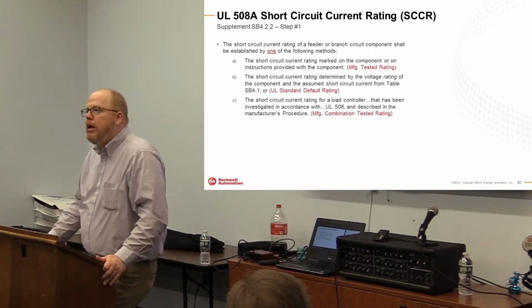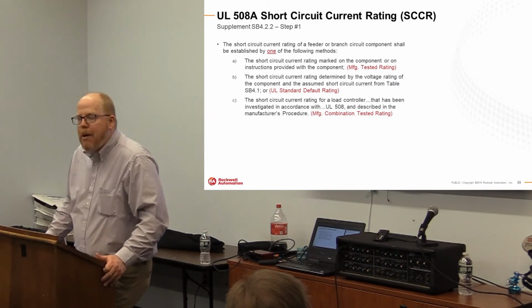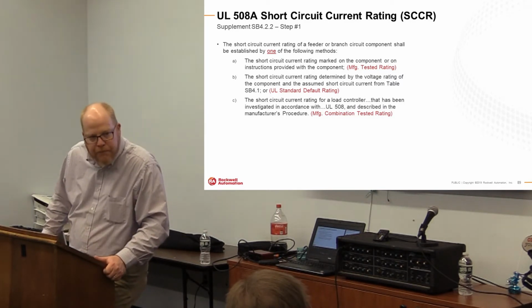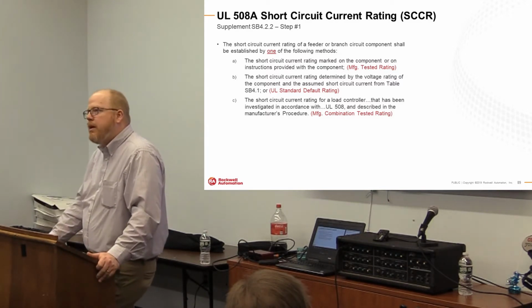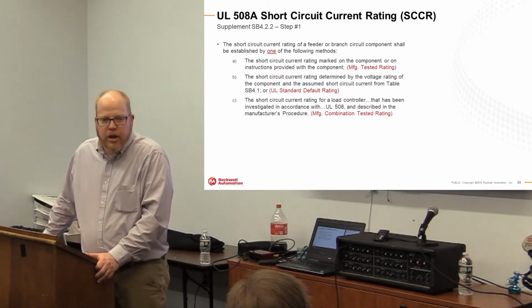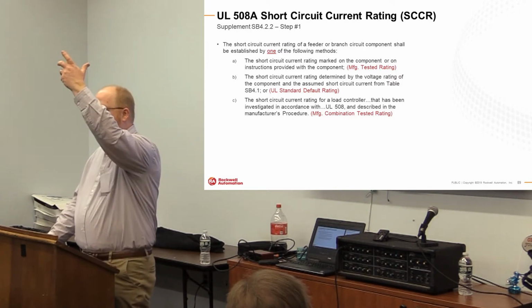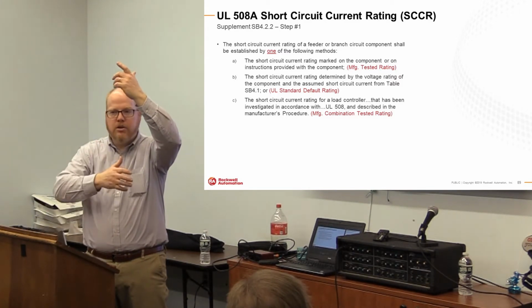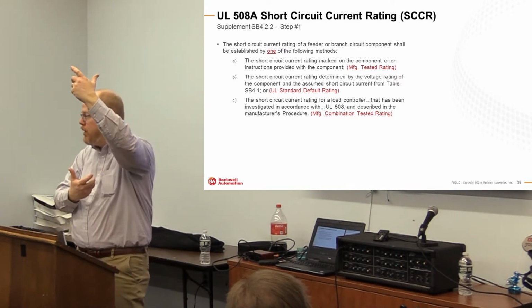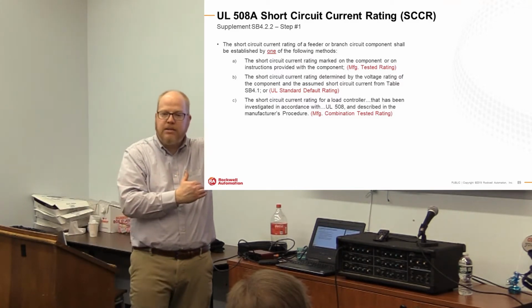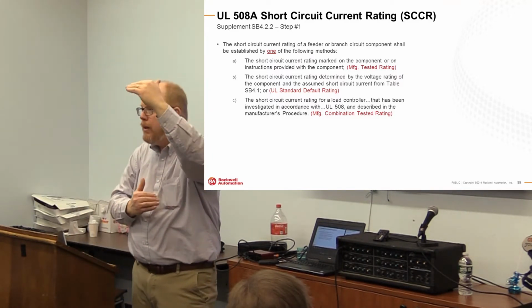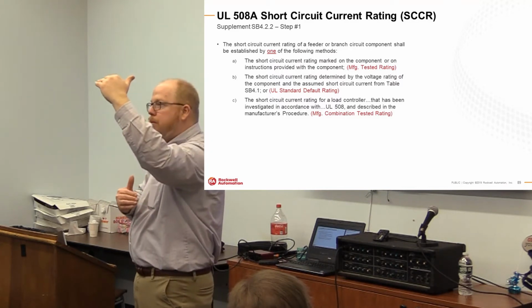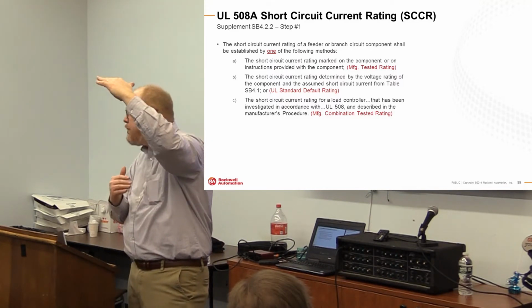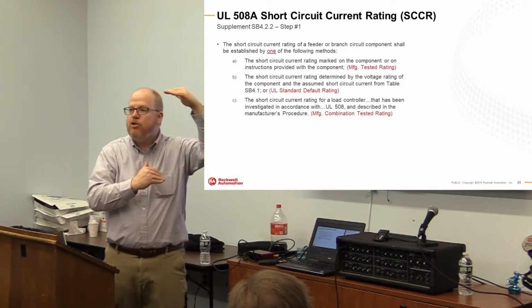The third step is the one that we prefer as a manufacturer, and I'm sure our competitors do as well. It's what we call the combination test rating. This is where we take a collection of branch circuit components, circuit protection with a contactor with an overload, which are 3 discrete components. We test them as a combination. You know, we basically blow them up in a lab, and then we can ascribe a combination rating to that assembly.